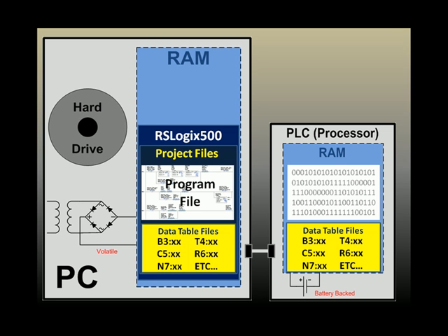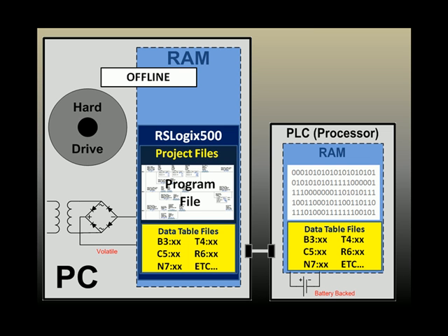When you begin writing your program, your programming software is going to be in the offline mode, and you are going to view the ladder logic program, that is the highlighted state of each instruction. That highlighted state is determined by the memory location, the value in that memory location that each instruction addresses.